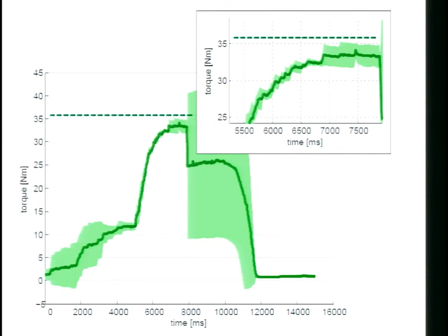This is the graph which shows that we have a consistent behavior. We can limit the torque below the 35 Newton meter level, which prevents the failure of the harmonic drive.